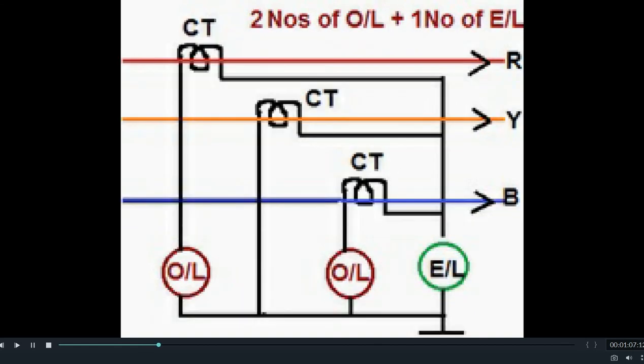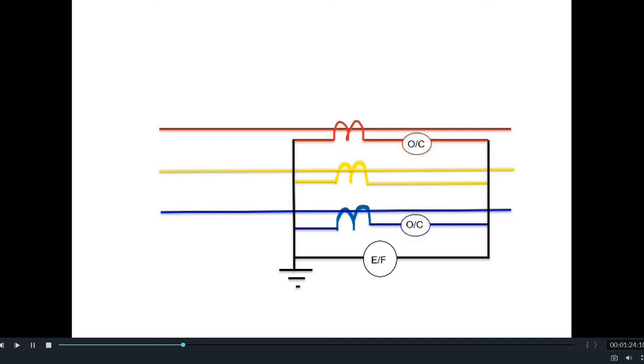So how do three overcurrent relays with one earth fault relay solve the purpose, and also how do two overcurrent relays and one earth fault relay in combination serve the same purpose? We will see this in the animation. Here we have considered a transmission line protected by overcurrent and earth fault relays in combination, with two overcurrent relays on R phase and B phase, and one earth fault relay in the star neutral of the CT secondary.